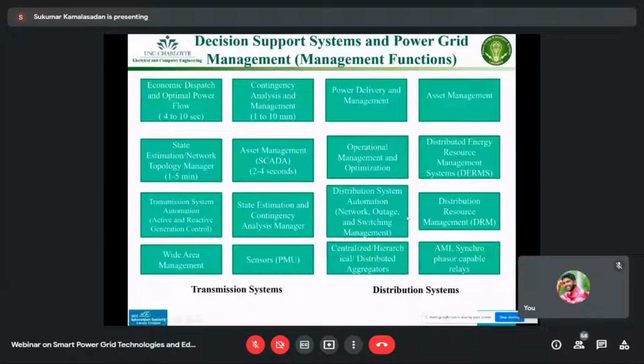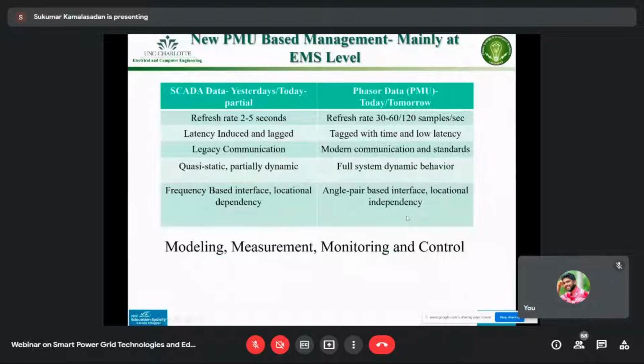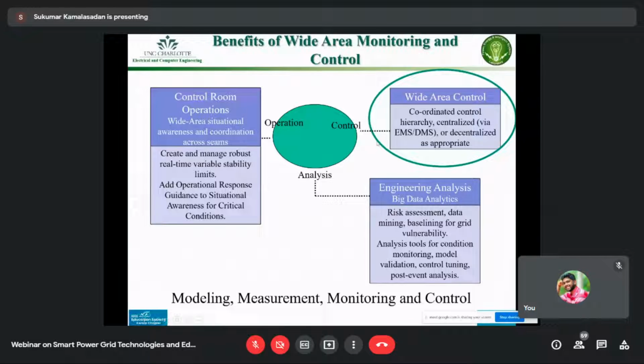On the distribution side, new management systems have emerged. So the way that you model, measure, monitor, and control has changed because of the advent of phasor data or phasor measurement units. It used to be SCADA-based; now we are going to have a measurement-based management system. The good news is that you can measure and manage it faster, with a faster time frame. The bad news is that you need enough resources to manage and control those devices with the measurements.